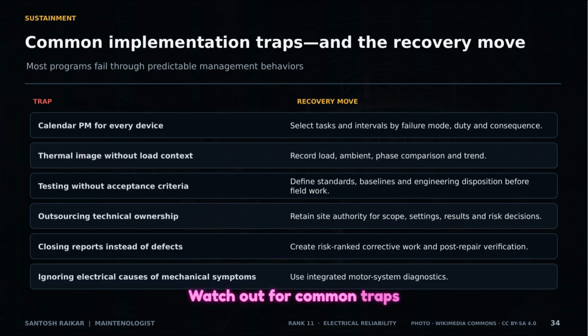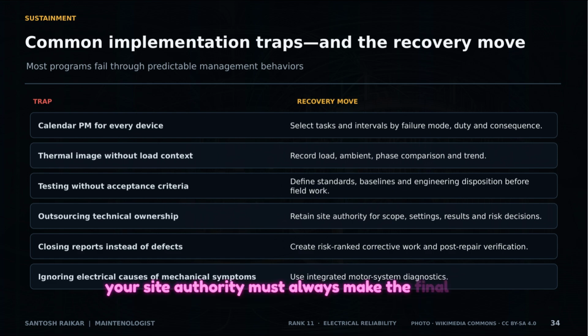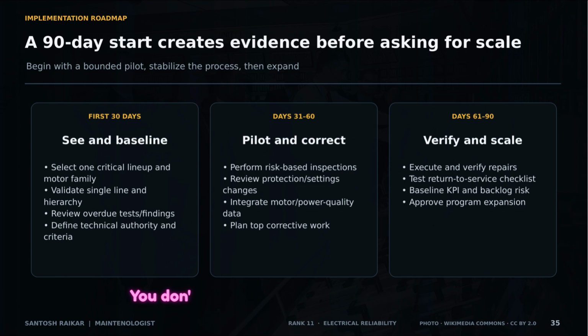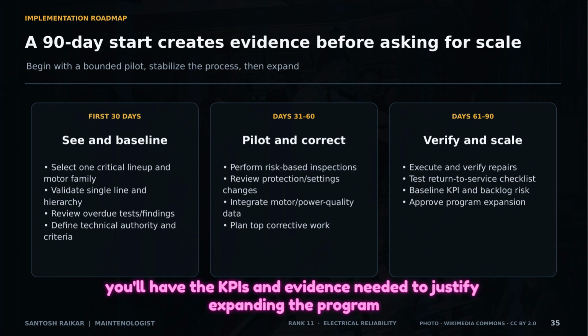Watch out for common traps. Don't just do calendar-based PMs on every device. Focus on failure modes. Don't take thermal images without recording the load. And never outsource your technical ownership. Your site authority must always make the final risk decisions. You don't have to change everything at once. Start with a 90-day roadmap. Use the first 30 days to baseline a single critical lineup. In the next 30, run the pilot and plan corrections. By day 90, you'll have the KPIs and evidence needed to justify expanding the program.